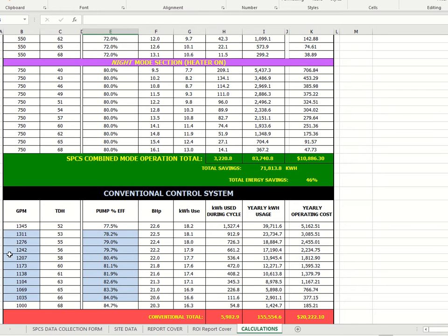This, when you get it, will already be sort of evenly spaced from your design point to your maximum flow, and it will also be evenly spaced for your percentage from design to maximum. This is going to be pretty close, and it would be applicable to most pump performance curves where the design point is at the best efficiency point and it goes downhill from there.